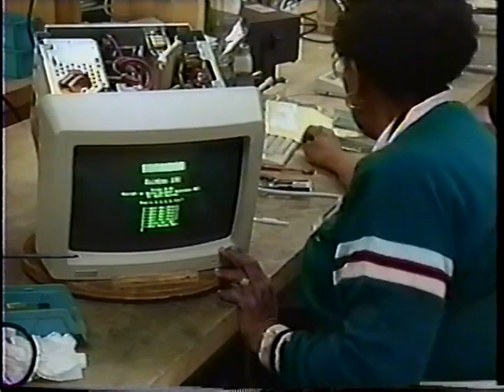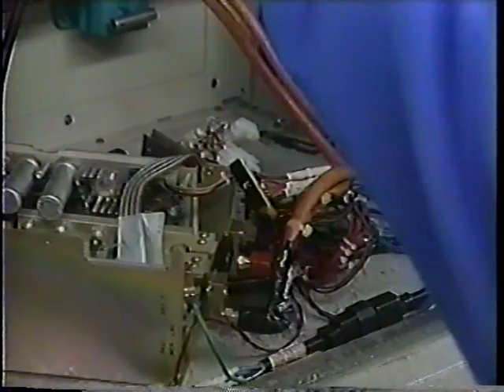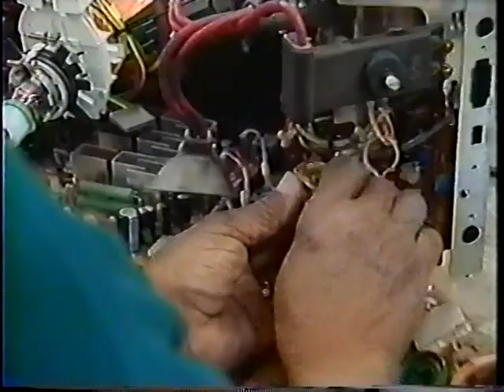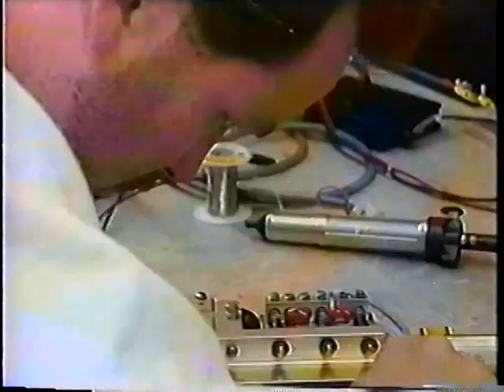High-voltage non-hazard workstations have no exposed metal parts where you could make contact with the high voltage. Interlocks, insulating barriers, and other devices are used to ensure that you can't make contact with a high voltage. Electrostatic discharge controls cannot be abandoned because of the presence of hazardous voltage. In situations where personnel cannot wear wrist straps because they may experience electric shock, static electricity must be kept under control. Of course, personal safety requirements take priority over ESD controls.